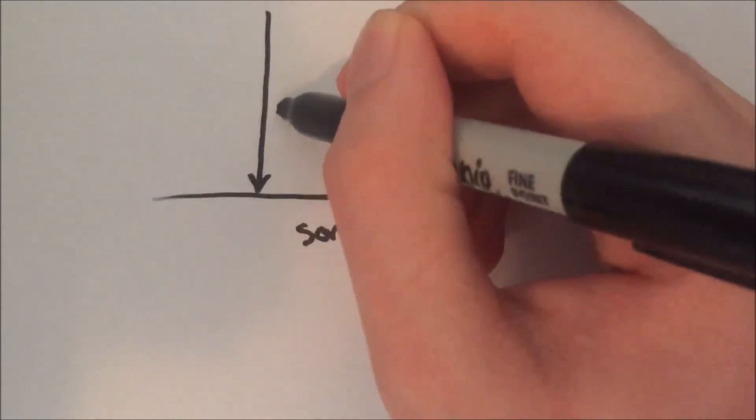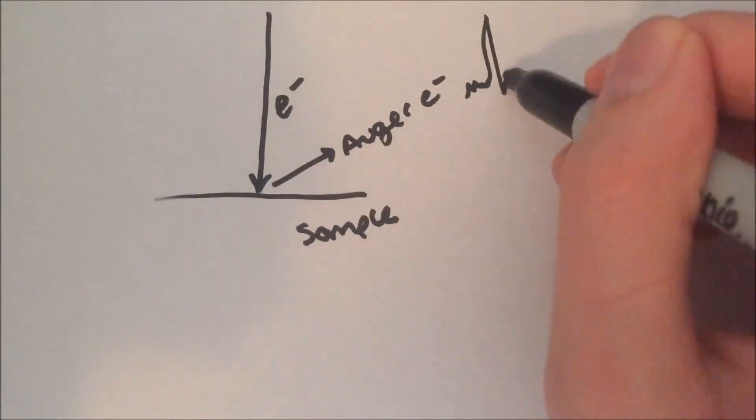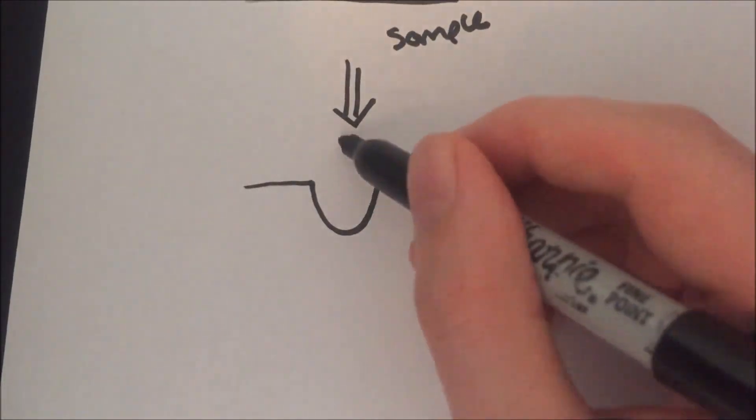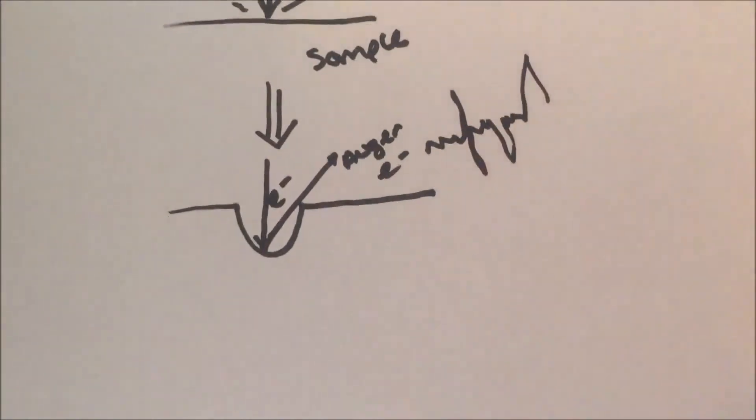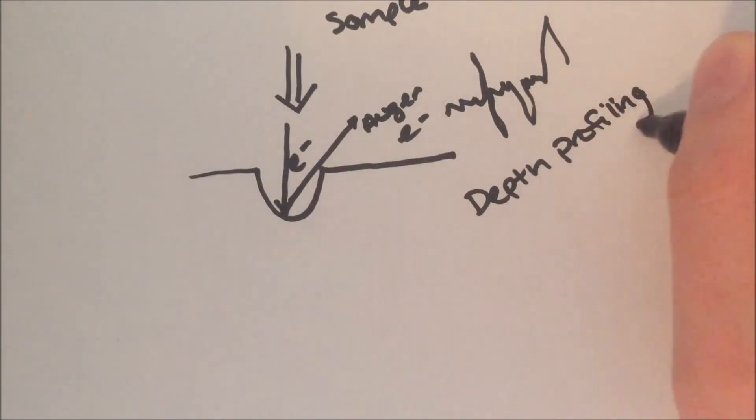Additional elemental information can be obtained through Auger spectroscopy by pairing it with a high-energy ion gun. This ion gun can be used to etch the surface of the sample, allowing for Auger electron analysis at a deeper region. This type of analysis can give very precise elemental information, but is destructive to the sample surface.